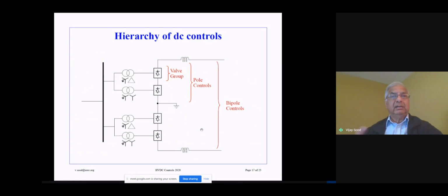So here is the hierarchy of the controls, the DC controls. So this is a bipolar DC system. We have 12-pulse bridges, two 6-pulse bridges in series, giving you a 12-pulse operation. Usually the transformer connections are indicated star-delta, delta-star for the upper bridge. Usually the neutral on the star point is grounded.